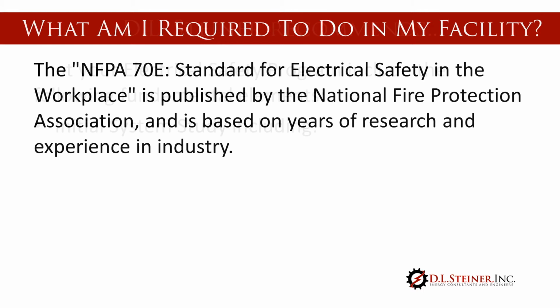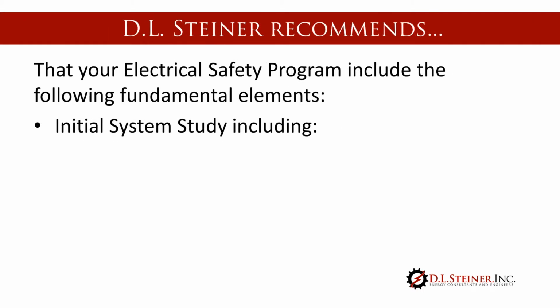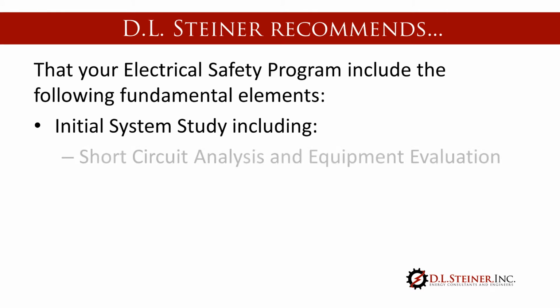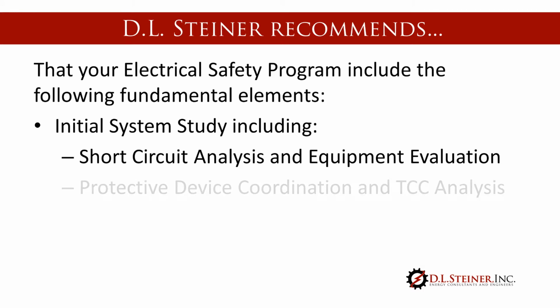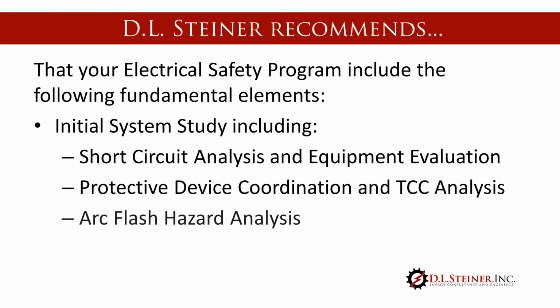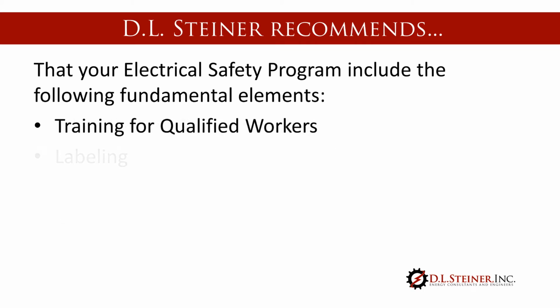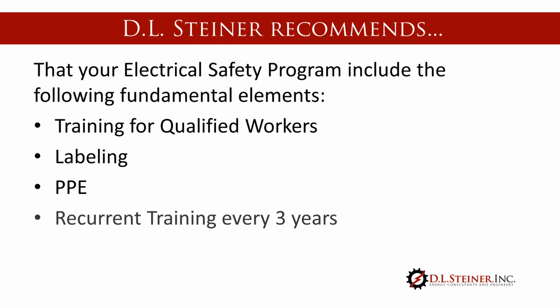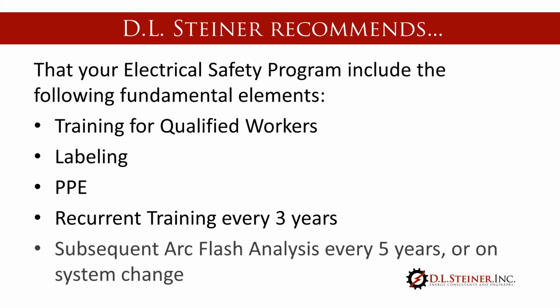DL Steiner recommends that your electrical safety program include the following components: an initial system study, including a short circuit analysis and equipment evaluation, protective device coordination, an arc flash hazard analysis, training for your qualified workers, labeling of your equipment, and proper PPE for employees. The NFPA 70E states that recurring training should be every 3 years, and arc flash studies should be updated every 5 years or after any major system change.